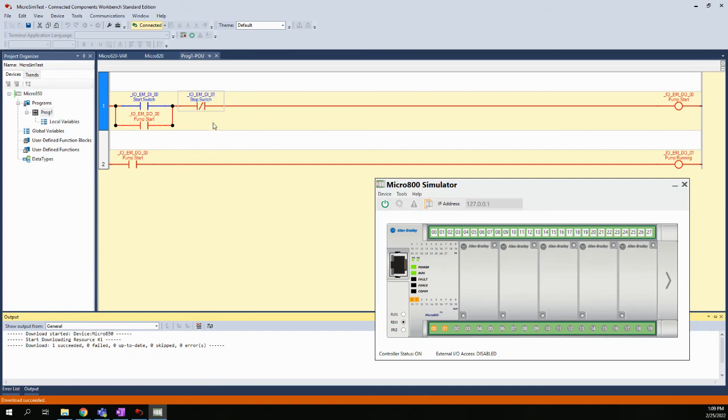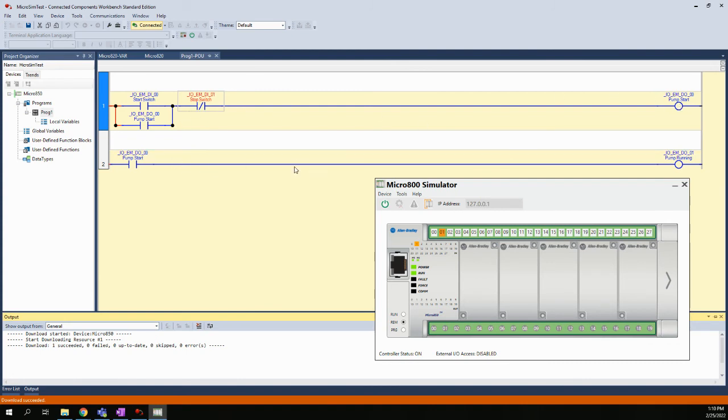I'm going to basically simulate pushing the stop button by clicking on the stop. Now when I do that, we broke power—we broke power to the pump start, so that dropped off. The coil dropped out, the second rung's coil turned off our two outputs, our two indicator lights went out. Then I let my finger off the stop switch and everything stayed off.